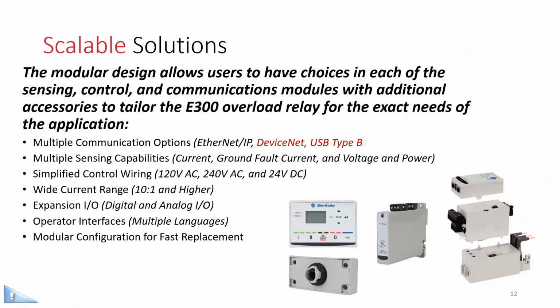The E300 was also designed to simplify control wiring. The user can select from 3 available control voltages: 120, 240, and 24 volt DC. It has a wide current range of 10 to 1, and just for reference, the old E3 Plus that this replaced had a current range of 5 to 1. So this minimizes the number of sensing modules that the customer needs to purchase.